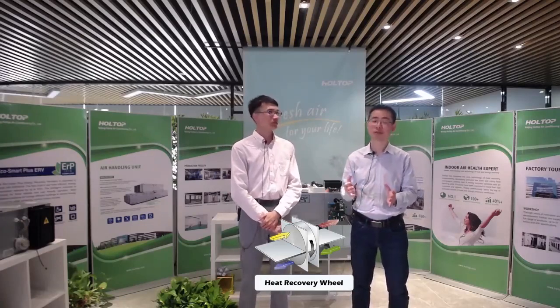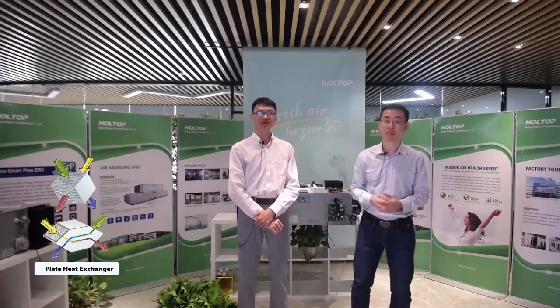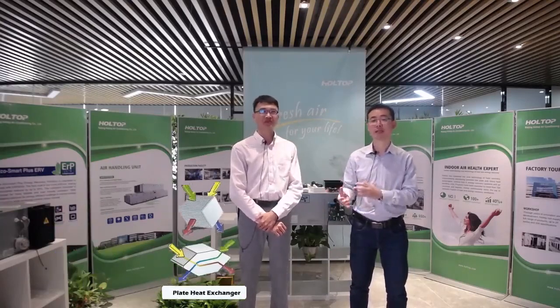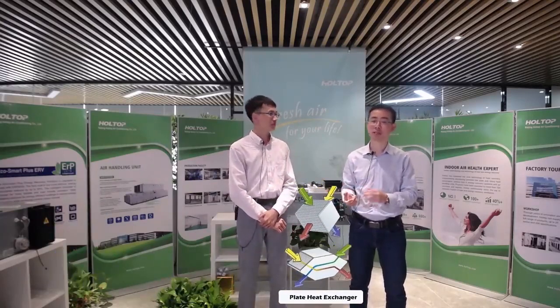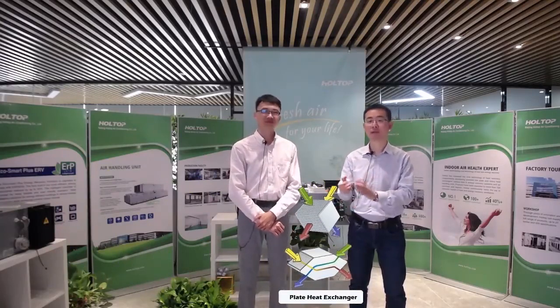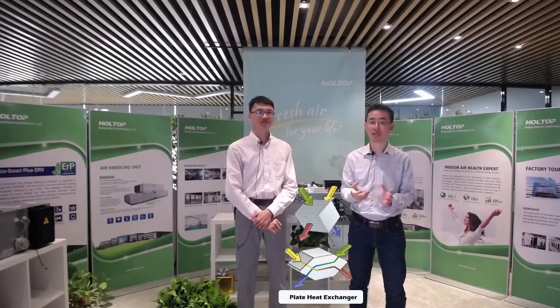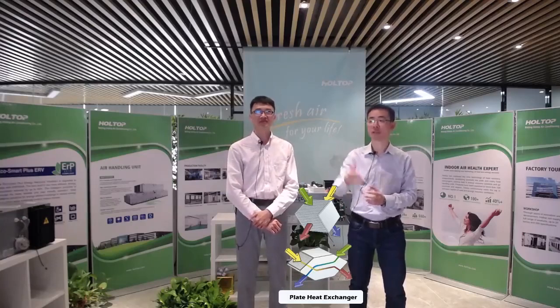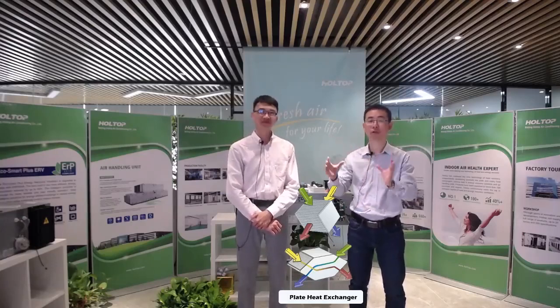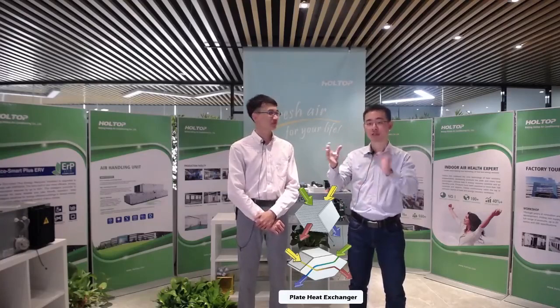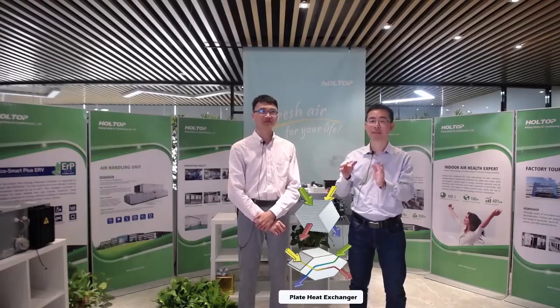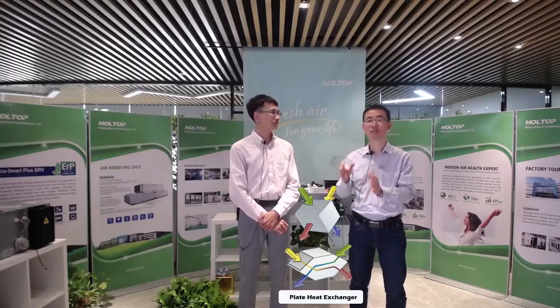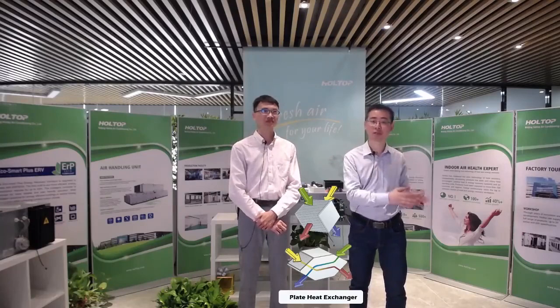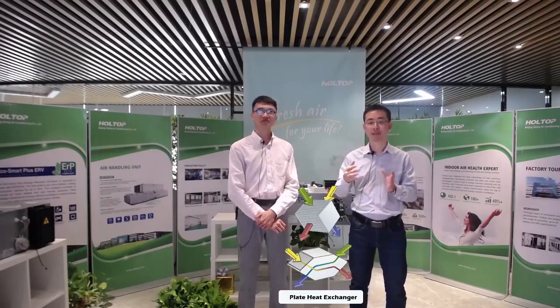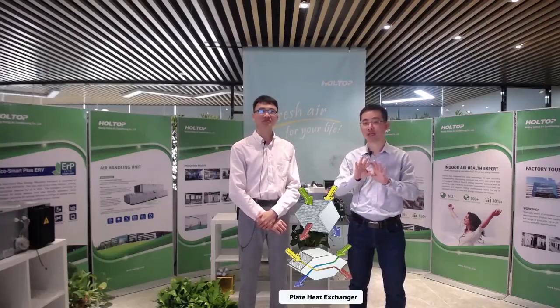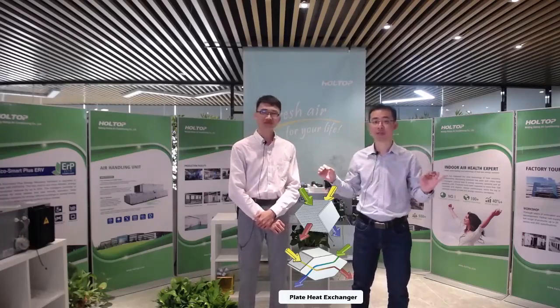The second one that I'm going to introduce is the plate heat exchanger. It is a plate type, and right now we have enthalpy type and sensible type. What I'm going to present to you now is the sensible type. Please show the picture of the sensible heat recovery core. As you see, this is a plate type, and the key feature is sensible heat recovery from the exhaust air to the fresh air, and the supply air and the exhaust air are 100% separate.